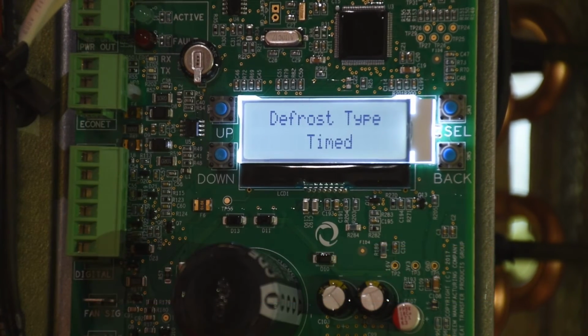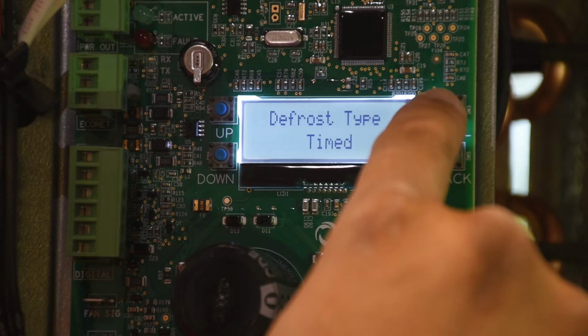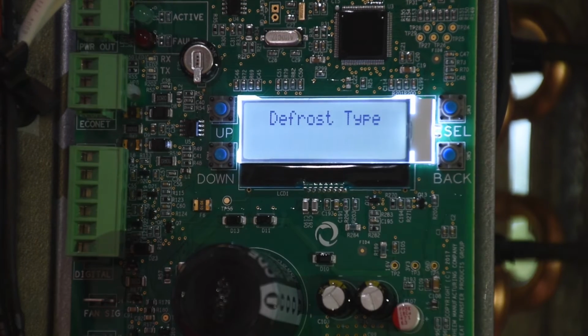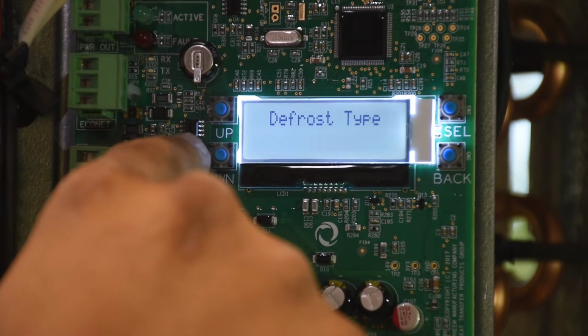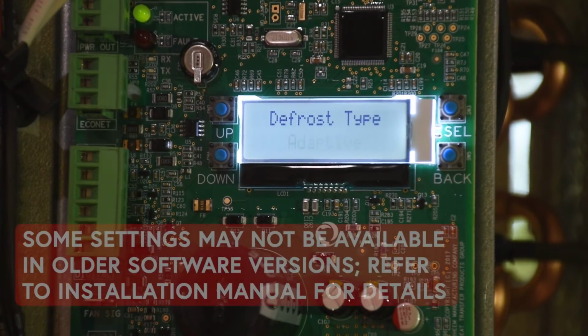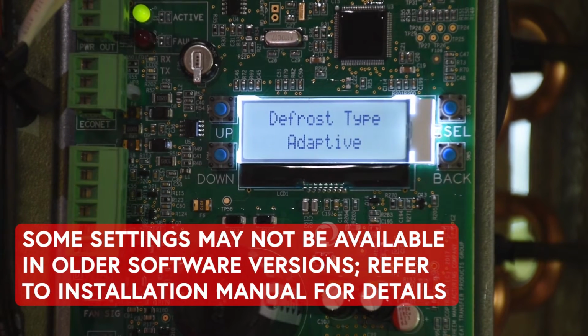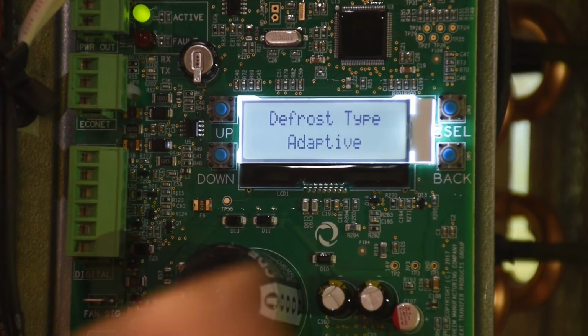There it is. So defrost type, default is time defrost, but if you want adaptive, again hit select, the word is going to start flashing, and then you just hit down for adaptive, and then hit select again to confirm the change. One thing on adaptive defrost, it only works on freezers, so the control has to be configured as a freezer with electric heaters for this change to actually take effect.